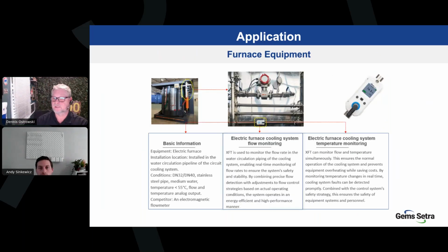Getting out of semiconductors and into something more industrial, furnace equipment. It was used in furnace equipment in place of an electromagnetic. The electromagnetic, you see it in the middle picture at the top there, quite large. It probably handles higher flows, but not necessarily. It could be something under 100 gallons per minute, and you just see the size difference, right? They use it for monitoring flow and temperature simultaneously. It was for a cooling system, preventing systems from overheating, okay?